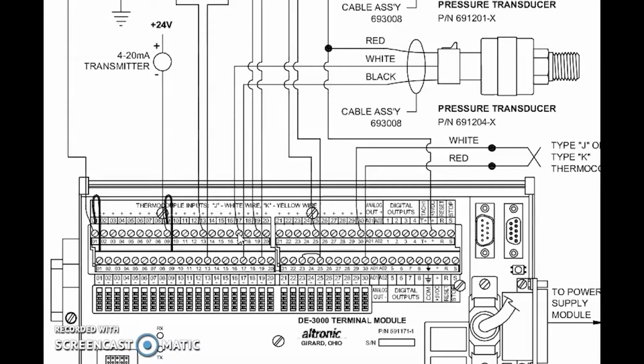Now, we call this a 0 to 5 volt pressure transducer, but actually it's a 0.5 to 4.5 range. So a good example is if you have a 0 to 300 pound pressure transducer, the actual voltage to pressure scaling is 0 psi G will equal 0.5 volts. If you pressure the transducer up to full range at 300 pounds, the voltage output will be 4.5 volts. Now, this is how we calibrate it by standard from the factory.